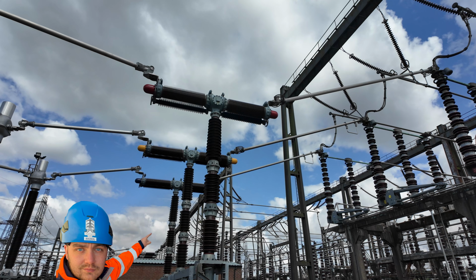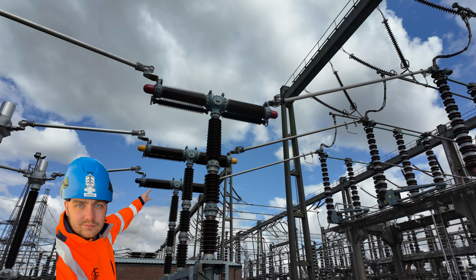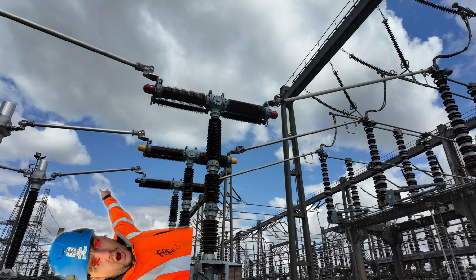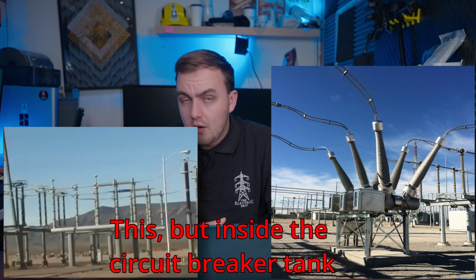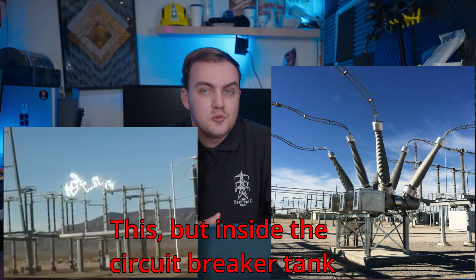A live tank, therefore, would have the whole thing supported up high, so you couldn't touch it, as it would be live and rapidly turn your liquids into a gas if you touched it. So not safe, and substations need to be safe by design because people like me need to work in them. Circuit breakers are essentially big switches that are engineered so that when we switch them under load and an arc forms between the contacts of said switch, we can extinguish the arc safely.